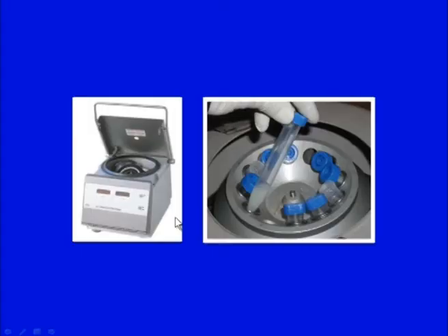All right, so what is done essentially in this, if you see this figure, is a very typical centrifuge, a bench top centrifuge. Essentially what I would like to show you is that there is a rotor inside, and these are tubes which are put in. To enlarge this, this rotor is placed on the central drive shaft of the centrifuge, which contains a motor to run it. The material or particle is suspended in a suitable liquid medium, and then this medium with particles is kept in these centrifugation tubes. These could be plastic tubes or glass tubes also, but glass tubes can crack when you are applying larger centrifugal force.